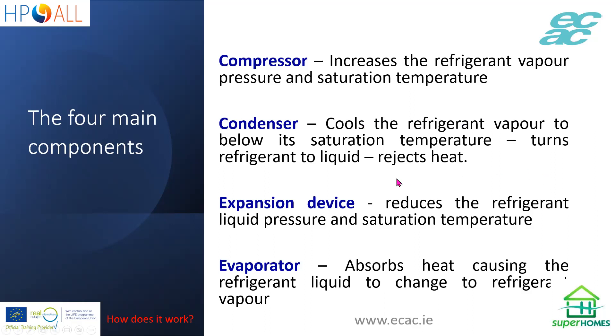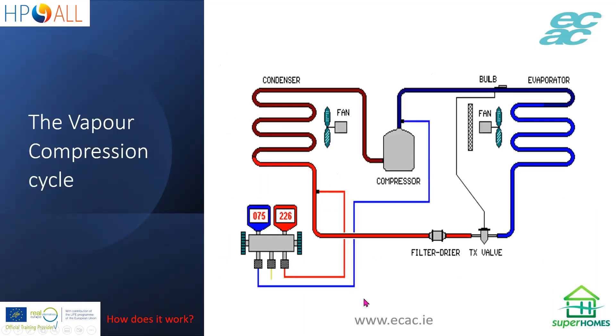The condenser cools the refrigerant vapor to below its saturation temperature — it's basically a heat exchanger. It's a passive device and not a whole lot can go wrong with it barring leaks, but it does have a big role to play in energy efficiency. The expansion device reduces the refrigerant liquid pressure and saturation temperature — it's basically the opposite of the compressor. And the evaporator absorbs heat, causing the refrigerant to change from liquid to vapor. That's our basic cycle.